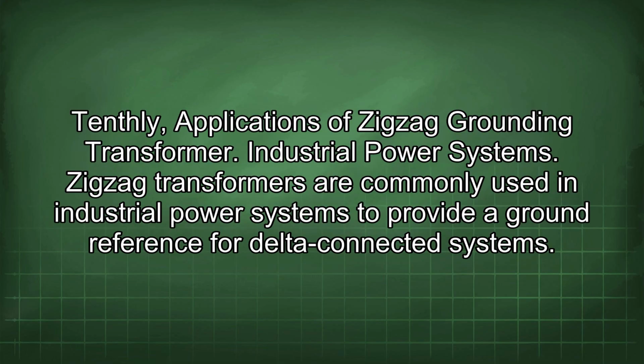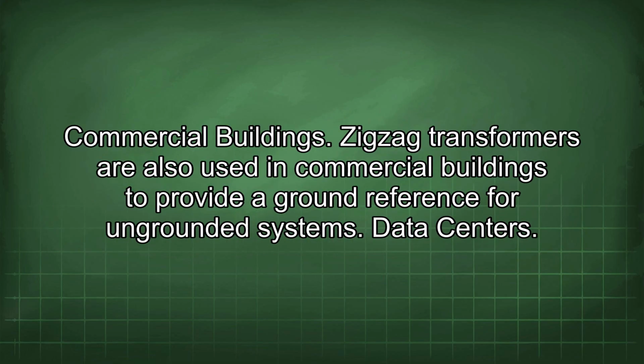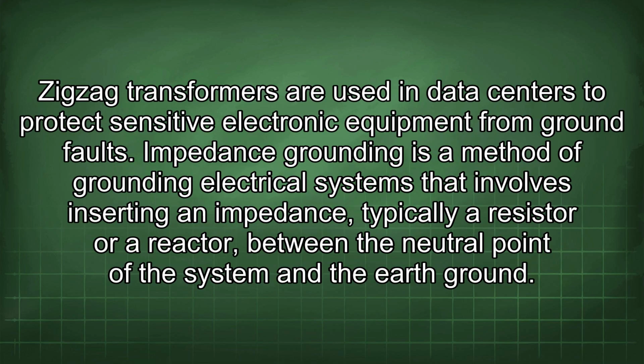Tenthly, applications of zigzag grounding transformer. Industrial power systems. Zigzag transformers are commonly used in industrial power systems to provide a ground reference for delta-connected systems. Commercial buildings. Zigzag transformers are also used in commercial buildings to provide a ground reference for ungrounded systems. Data centers. Zigzag transformers are used in data centers to protect sensitive electronic equipment from ground faults.